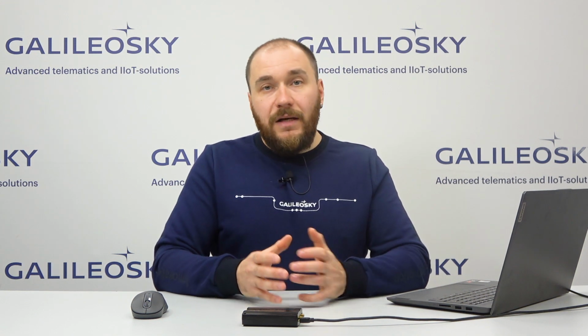The tracker and the computer running the OPC server must be in the same network, and this network might be virtual. The OPC server addresses the tracker by IP, so it is better to configure the DHCP server of the network so that the same IP address is always given to the tracker by its MAC address. You can always find out the tracker's Wi-Fi MAC address in the configurator on the device tab. Now let's see how the OPC server is configured.